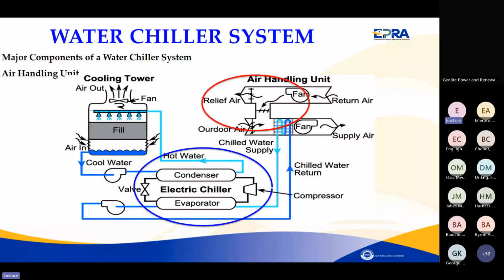But now, in energy auditing, what you need to establish first is the cooling load. How much cooling do you want? So in your measurements, you have to establish the outdoor temperature conditions. You have to establish whether the internal conditions are well maintained, and you measure the conditions of the air released, that's the temperature of the air being released from the room. Once you establish that, you establish the cooling load of the room and see whether it is matching the design of the water chiller, so that you can know whether it's being underutilized or sometimes overutilized. But if it's being overutilized, it won't achieve the conditions.